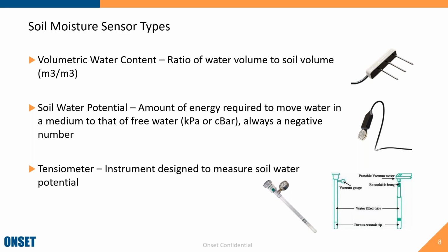This is a measurement of interest mostly because it's independent of soil type. Different soil types retain water differently. For example, sand gives up water much more easily, so you need less water for the plant to sustain itself. It also clears hurdles in terms of salinity and things of that nature. Tensiometers are instruments designed to get a similar type of water potential measurement, just done differently and in more of a local type of device.